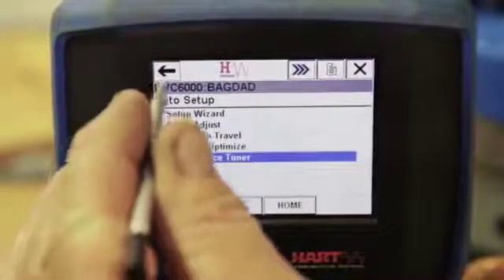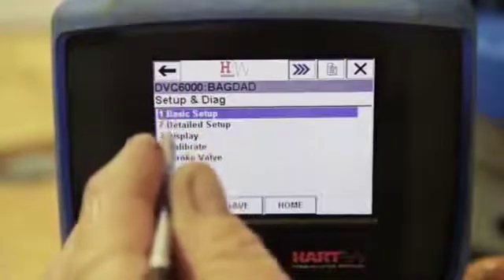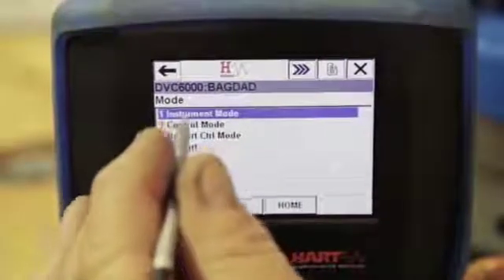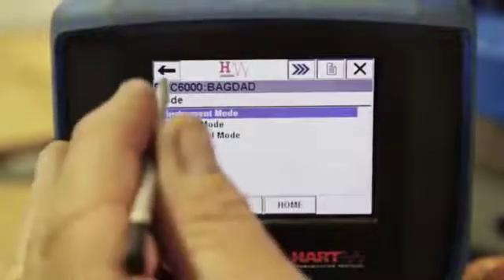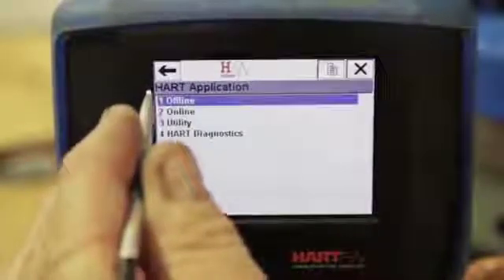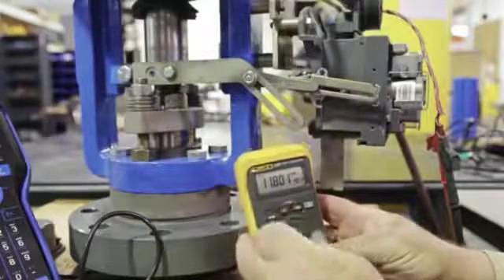Arrow back to the Setup and Diagnostics screen to put the instrument back in service. Select Detailed Setup, Mode, Instrument Mode. A warning that the valve may move when in service mode will appear. Put the instrument back in service and select Yes. Arrow back to exit out of all the screens. Select Yes to exit the HART application. Calibration is complete and the valve should function normally with instrument signal.